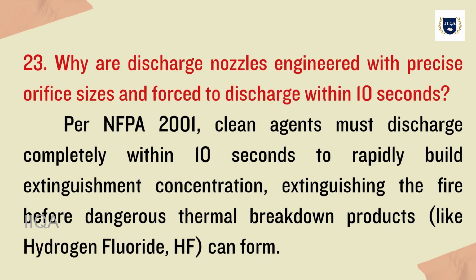23. Why are discharge nozzles engineered with precise orifice sizes and forced to discharge within 10 seconds? Per NFPA 2001, clean agents must discharge completely within 10 seconds to rapidly build extinguishment concentration, extinguishing the fire before dangerous thermal breakdown products, like hydrogen fluoride, HF, can form.